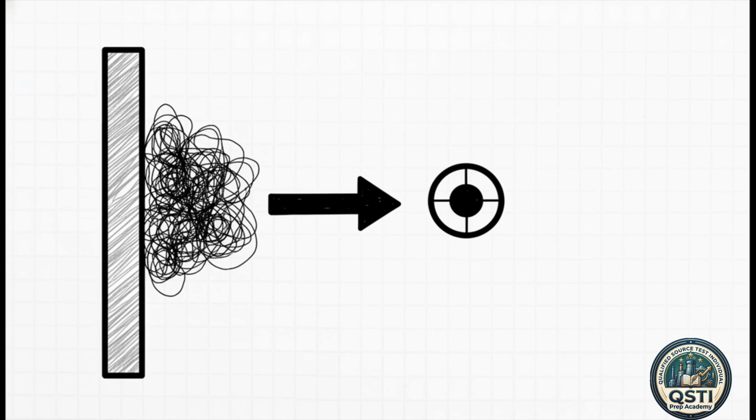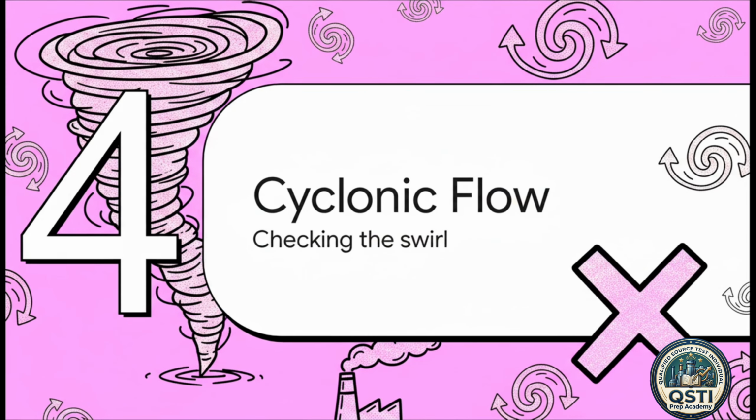And hey, before you start drilling any holes, you've got to remember the wall clearance rules. You literally cannot sample right up against the metal. The friction on those stack walls slows the air down and will totally wreck your data. If your stack is over 24 inches, stay at least 1 full inch away from the wall. If it's 24 inches or smaller, you still need a 1/2 inch of clearance. If you calculate a point and it lands closer than that, you have to bump it inward to the adjusted minimum distance. Finally, Section 4, checking for cyclonic flow.